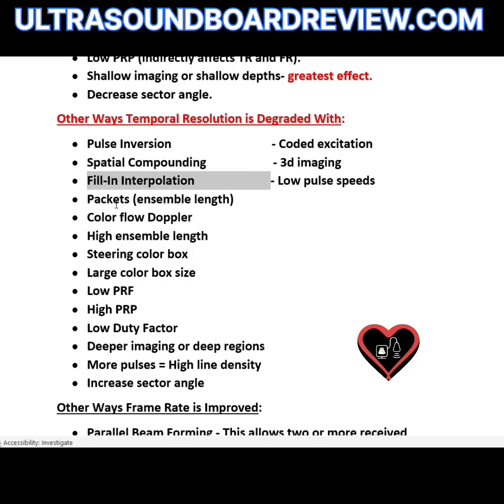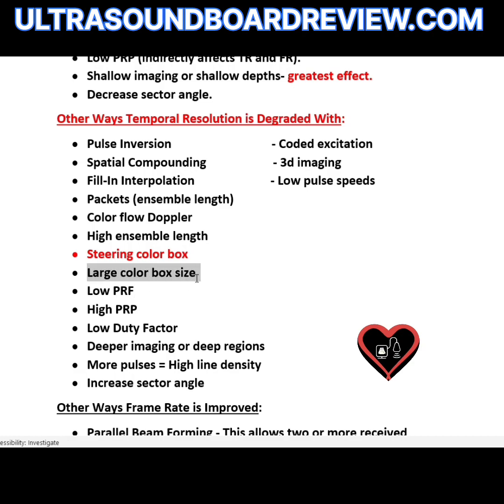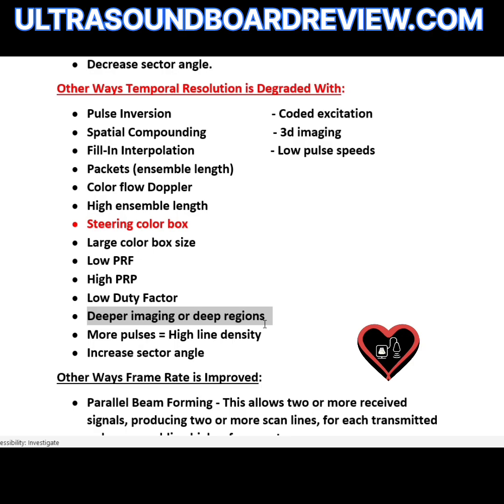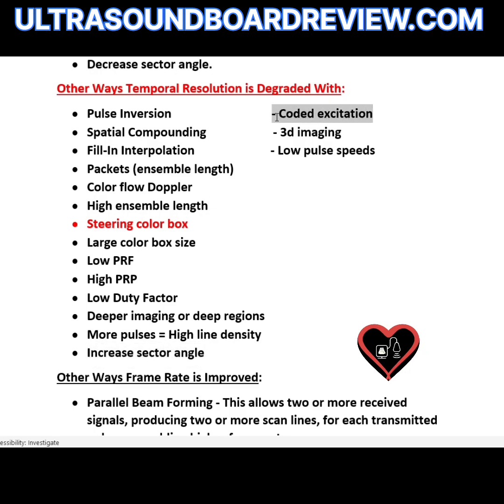Other things that degrade temporal resolution include: spatial compounding, fill-in interpolation, high packets or ensemble length, turning on color Doppler (keep the color box small to the area of interest), steering your color box, having a large color box size, a low PRF, a high PRP (PRF and PRP are inversely related), scanning in deeper regions, having more pulses or high line density, increasing your sector angle, coded excitation, 3D imaging, and low pulse speeds.